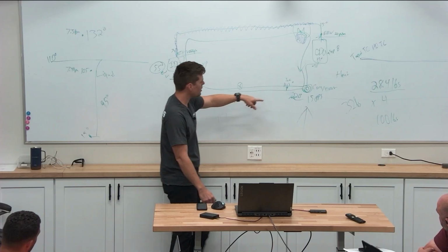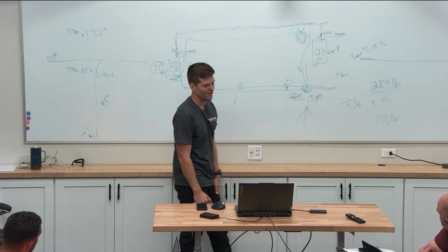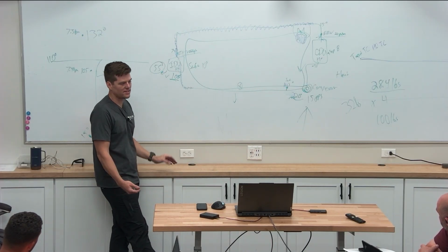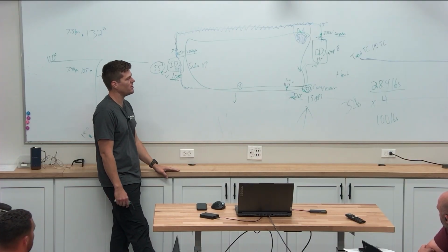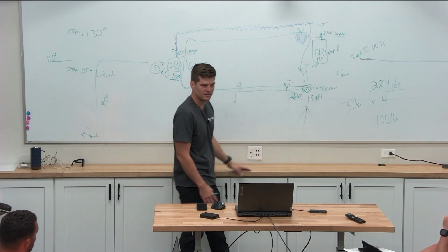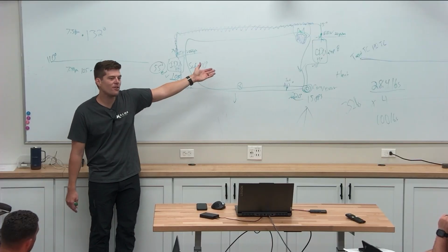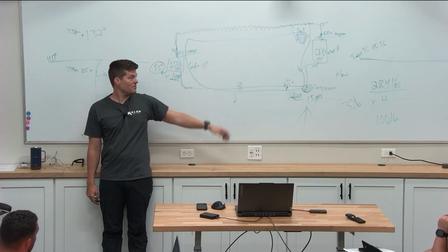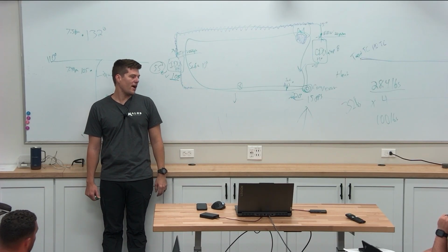Is it supposed to be a liquid on my suction line? No, it's supposed to be a vapor. And I go, okay, well, why? Why is it that way? Well, it's pinched off closed, doing everything it can to keep it from getting back to the compressor. Maybe they've got the outdoor unit wrapped in a tarp, and I'm not getting any air across my outdoor unit. There's a lot of other mitigating factors that can take place.